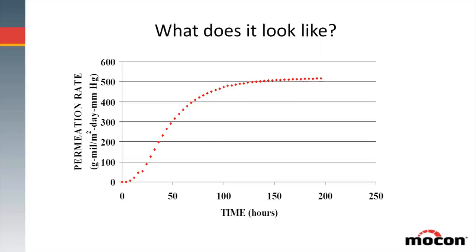People often ask what does permeation look like. Well, these water vapor molecules move into a package wall, get absorbed into it, and then come out on the other side. When you start a test where the material is totally void of water vapor, you won't see anything come through on the other side. The graph shows what we measure on that other side: it comes up slowly, and then over time we reach an equilibrium level. That's what we're normally measuring — that equilibrium level. So it's very common to see this uptake curve to reach equilibrium.